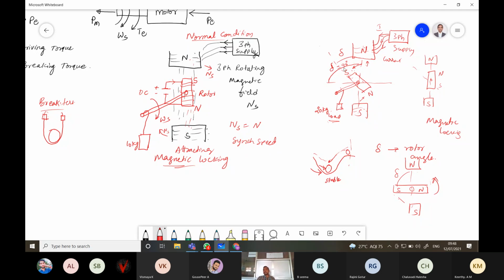So if the delta is more than 90 degrees, we are not getting the magnetic locking. More than 90 degrees, it will collapse. We are not achieving the stability because of the overload condition. Overload is one type of fault.